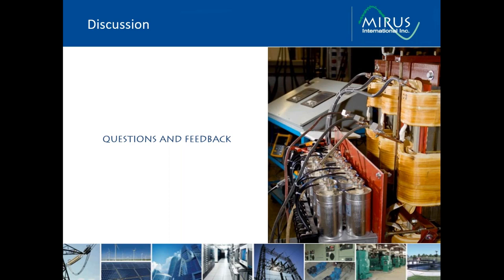Do you suggest usage of a harmonic filter with power factor correction at the bus? What precautions should be taken when engineering a filter to such requirement? Okay, in many applications, the removal of harmonics will actually restore the power factor to near unity and is often the only requirement to increase power factor. There are certainly some applications where the reactive power and lower power factor is the result of inductive loads or displacement power factor. An example of that would be a thyristor bridge operation or fixed speed motors.